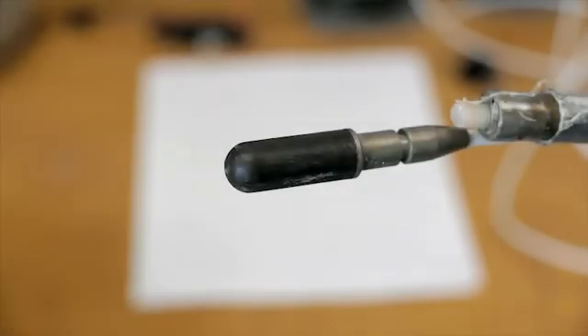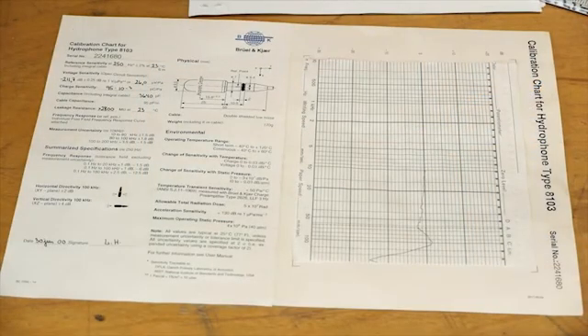The hydrophone that will be acting as our unknown transducer is a B&K type 8103 hydrophone. It measures about 2 centimeters in length and about 1 centimeter in diameter. It's a simple type of hydrophone that uses a piezoceramic cylinder that is radially polarized and then potted in a urethane rubber compound. We have a data sheet for the B&K 8103 hydrophone. It includes the open circuit voltage sensitivity, in this case in decibels referenced to 1 volt per micropascal. This calibration is done at 250 hertz, but there's also a chart showing the sensitivity versus frequency.